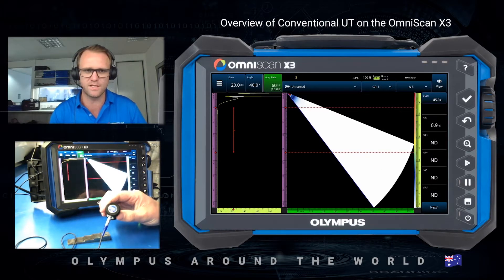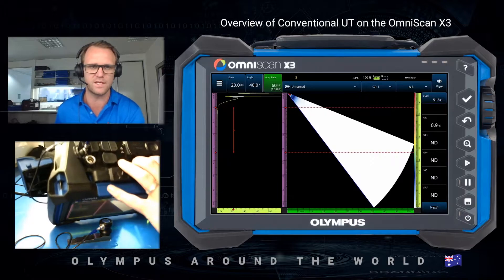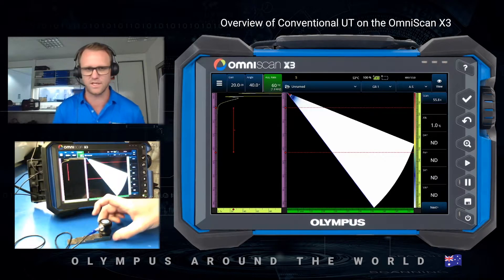To do that I'm just going to use a zero degree contact probe. This one is the CN4R-10 and I have it connected to the conventional UT channel on the OmniScan X3 using the LEMO connector. I'm also using a steel step wedge.